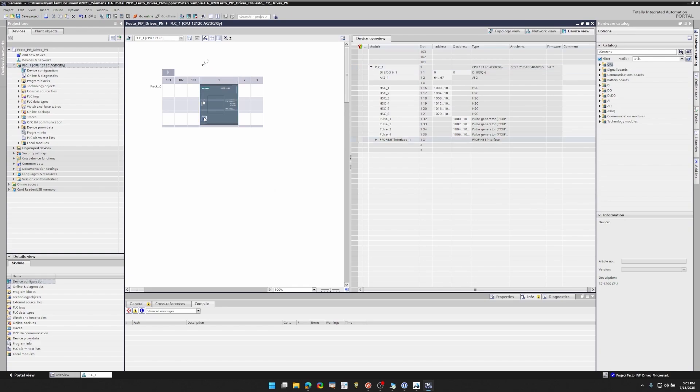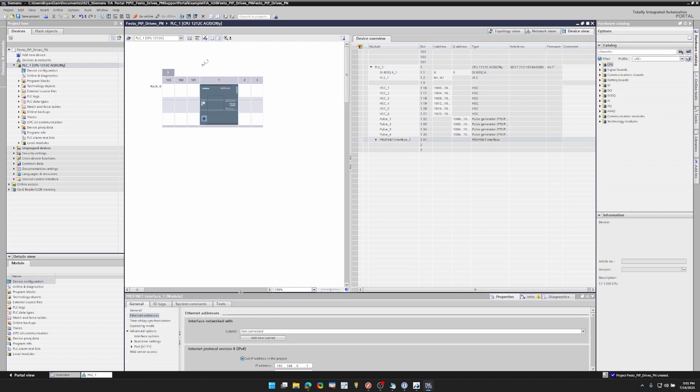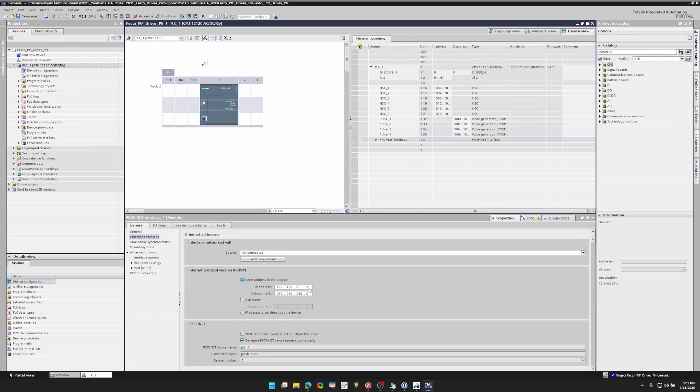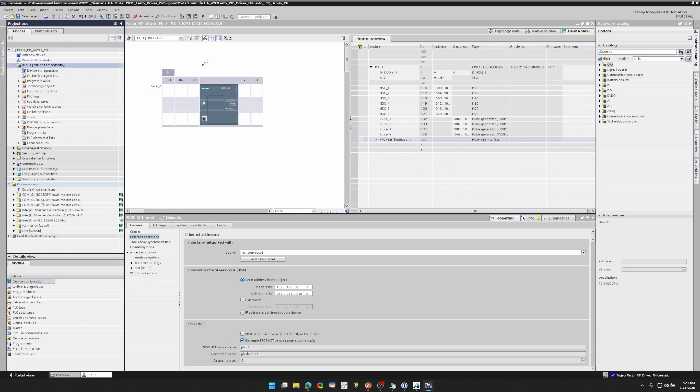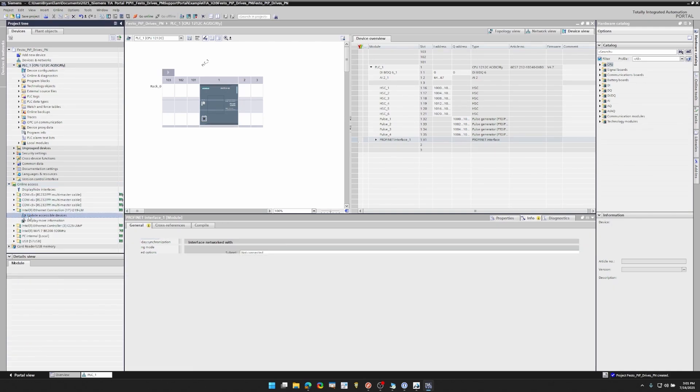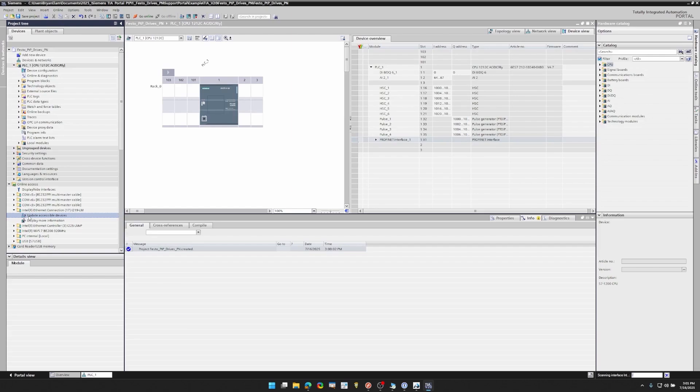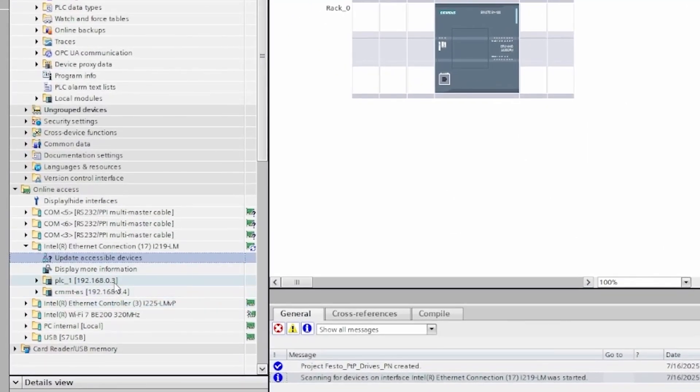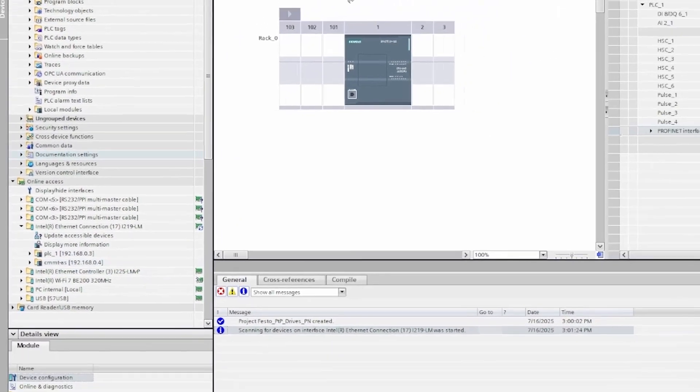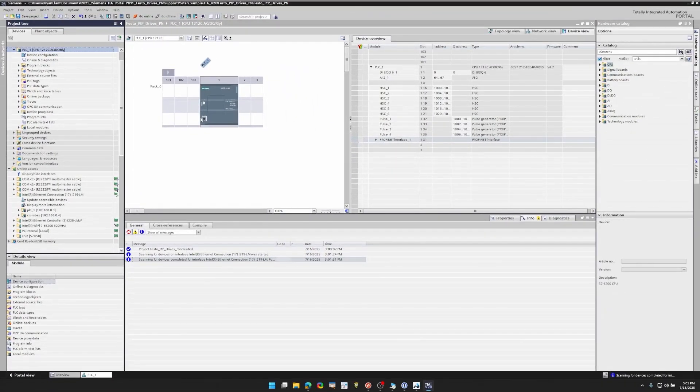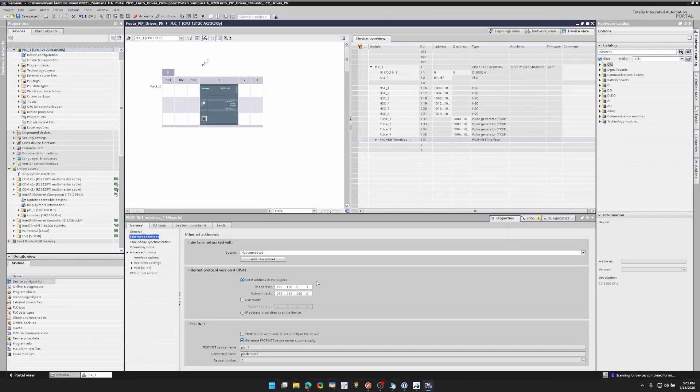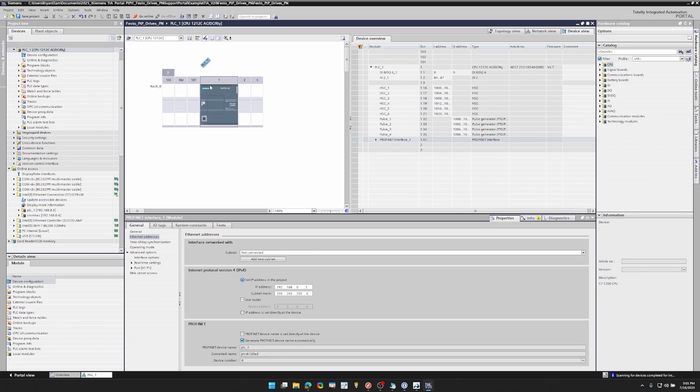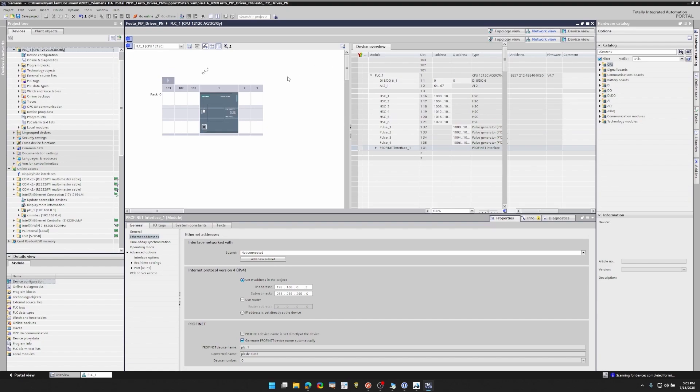Alright, double-click your Ethernet port and we're going to go ahead and set our IP address. If you forget what it is, you can go to online access, go to whatever your network switch is, hit update accessible devices. And there's my PLC and my servo drive right there. Alright, double-click the Ethernet port, change IP address. The other thing is you want to make sure you assign your ProfiNet name and that's just something that you have to do or you won't be able to communicate properly.